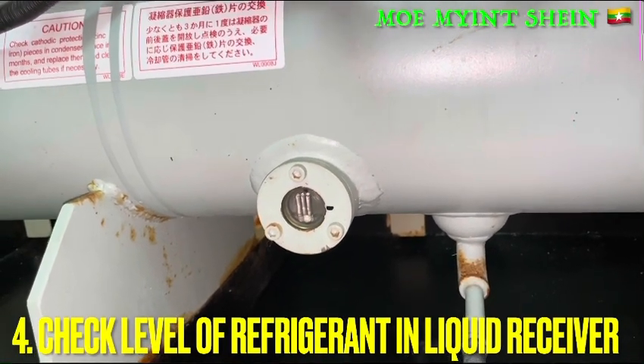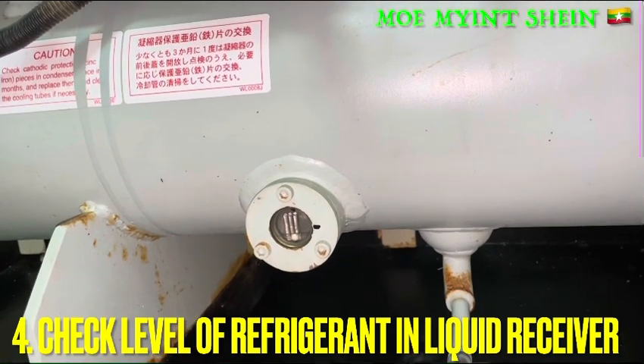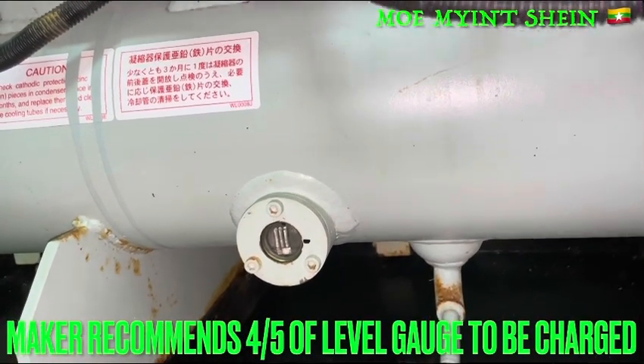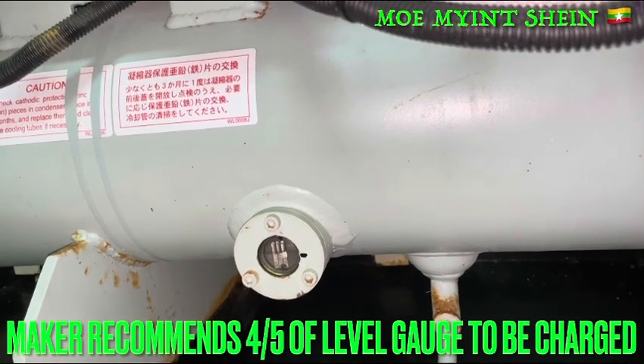Need to monitor the parameters of the high pressure, low pressure, amps of the compressor, and temperature difference of the cooling water between the inlet and outlet of the condenser. Check the level of the refrigerant from the sight glass. Make sure the recommended level is at 4/5 of the liquid level gauge.